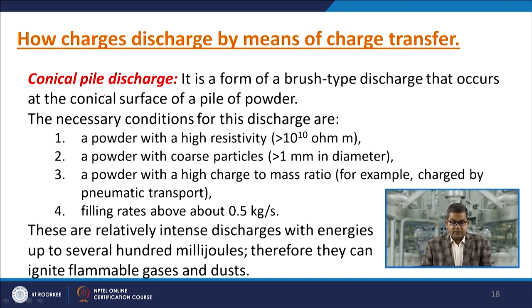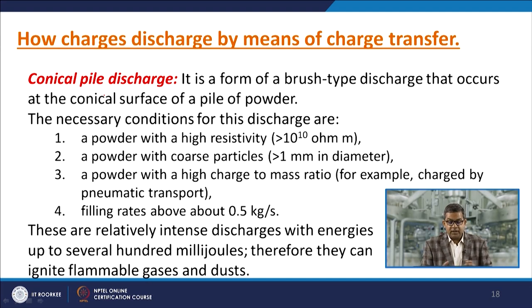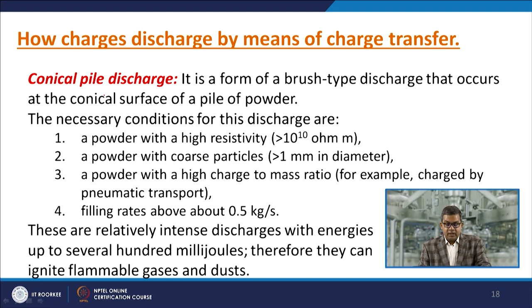Conical pile discharge is a form of brush-type discharge that occurs at the conical surface of a pile of powder. Necessary conditions include a powder with very high resistivity, coarse particles, a high charge-to-mass ratio, and filling rates above 0.5 kilograms per second. These are relatively intense discharges with energies up to several hundred millijoules and can therefore ignite flammable gases and dust.